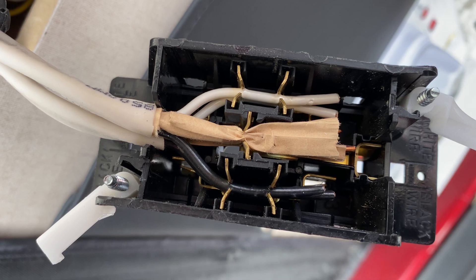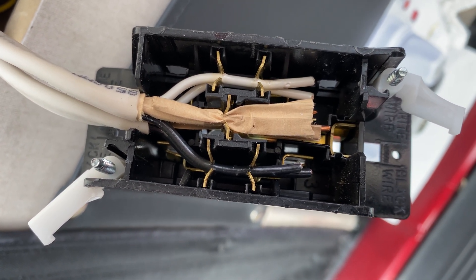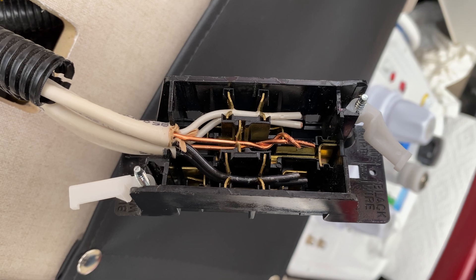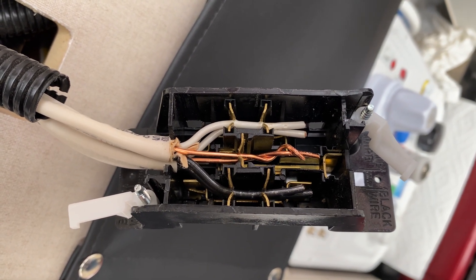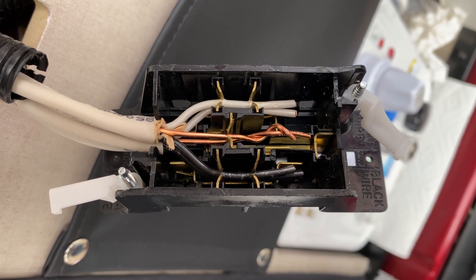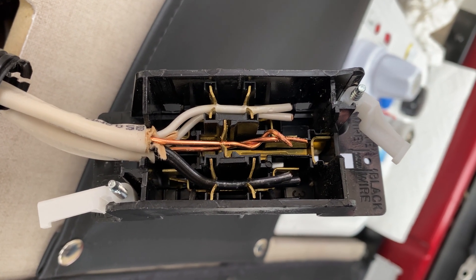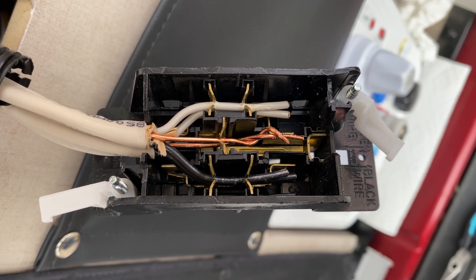How do you know if there isn't an interrupted contact there, especially with the ground wires? Removing the paper insulation on the ground wires, twisting them together a little bit, and pushing down on the white and black wires did nothing to change the GFCI tripping. I even checked continuity between the two white wires and the two black wires — there is continuity, so they are in fact in contact with the gold clamp in the middle. So it's not this outlet, as far as I can tell.